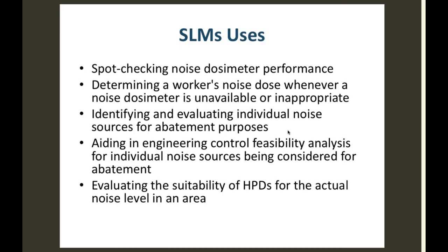Again, the only thing that OSHA is concerned about is 8-hour time-weighted exposure for determining whether there's a permissible exposure limit. So you can take a short-term measurement to get a rough idea, and maybe you have a high level of confidence that it's always going to be below that level, and you decide not to do individual monitoring. But if it's anywhere near close, the only thing that counts is individual monitoring.